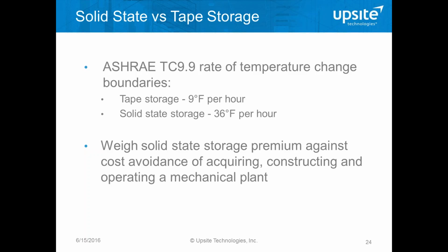And this really has to do with strictly the requirements for rate of temperature change. And these are not absolute numbers here. For example, if we were looking at a 2-degree temperature change in 10 minutes, that exceeds the 9 degrees per hour rate of change, and so that would be unacceptable. And so we can see in many parts of the country, if we're doing free cooling in areas where we get rapidly moving weather fronts with pretty good temperature differences on the leading and trailing edges of those fronts, that we would not be able to accommodate these kinds of changes.